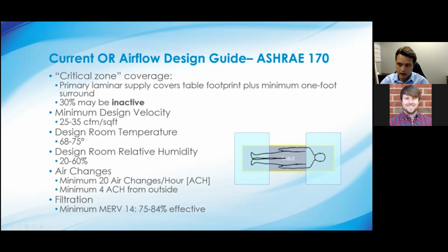The minimum design velocity of 25 to 35 CFM per square foot. A CFM per square foot is not exactly a unit of velocity. The math comes out to feet per minute, but it's written in the code as CFM per square foot because they wanted it to simply be a design guide where you could say, all right, I have X amount of CFM divided by Y amount of nominal square feet of diffuser. I fall within this range, therefore I'm good. This is not meant to be an actual metric that is to be measured. They didn't want somebody coming in with a device and actually measuring how fast the air was moving out of the diffusers or even around the patient. It's simply a design guide.